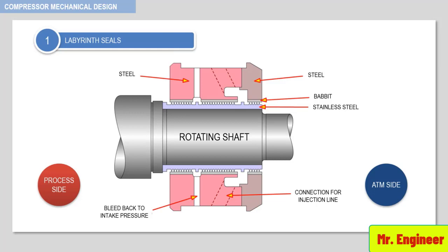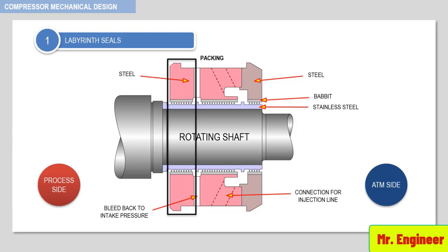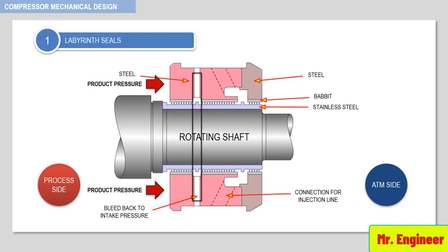You can see in this example that the labyrinth is divided into several sections. The first section is the packing, which is exposed to process pressure. A port or lantern is used to bleed off gas after the first section. This port is connected to the compressor intake.